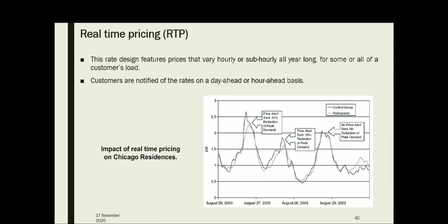Then real-time pricing. This is the purest form of dynamic pricing, and the scheme with the maximum uncertainty and risk for the consumers also. Here the prices change at regular intervals, sometimes every 1 hour or a few minutes. Even within a few minutes the price of the energy will change. So the change in the price in such a small interval increases the efficiency of the pricing scheme in reflecting the actual cost of the supply.